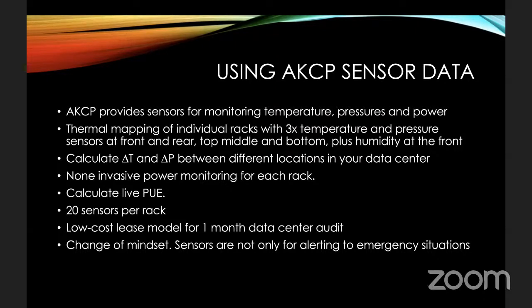The point is that the sensors are not an insurance policy. They are not only there to make sure that your server doesn't overheat. They're not there just to alert you when there's a problem. They are a tool that can be used to balance your pressures, to balance your delta Ts, and to make sure that your data center is running efficiently. And an efficiently running data center means it's got a lower carbon footprint, it's consuming less energy, it's costing you less to run, it's consuming less water. Ultimately, it may also mean that you can increase your server capacity without having to increase your cooling capacity.